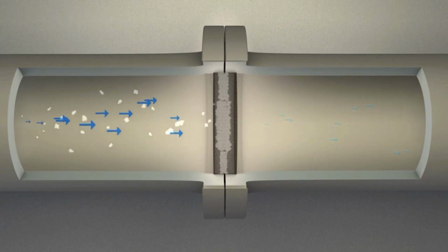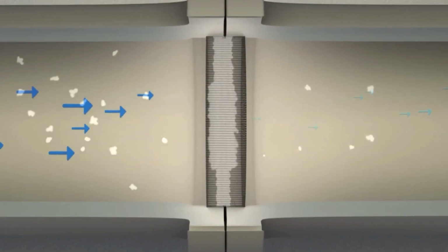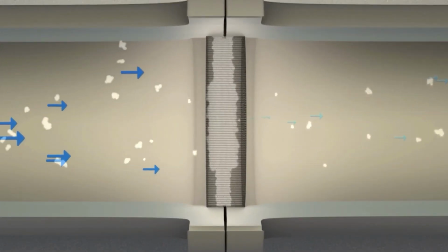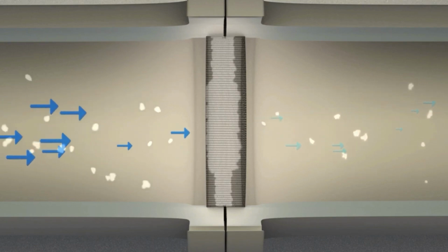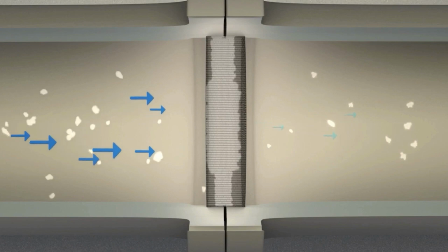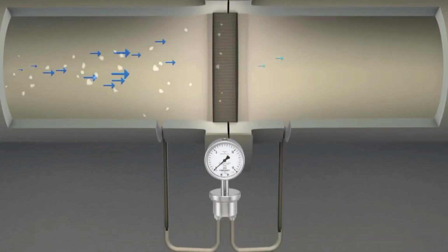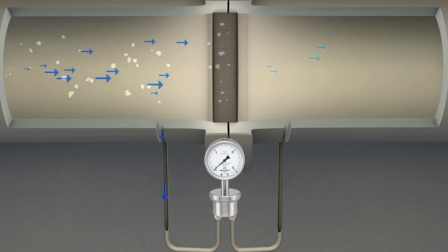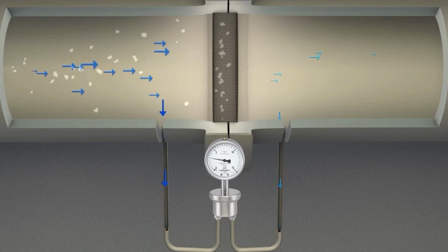Contaminants or particulates that build up in the filter will reduce media flow. As the filter becomes clogged, the downstream pressure drops. This results in an increased differential pressure, also referred to as the delta P. Saturated filters may also begin to shed captured particles, and with the filter no longer functioning properly, the contaminants can escape into the process. This is why proper monitoring of pressure drop is crucial.